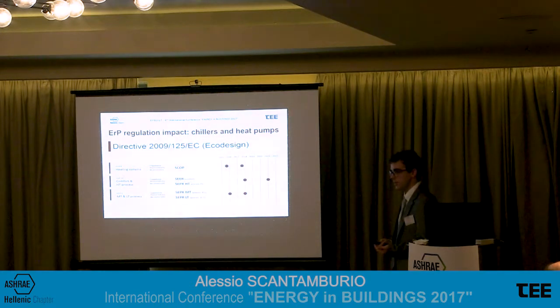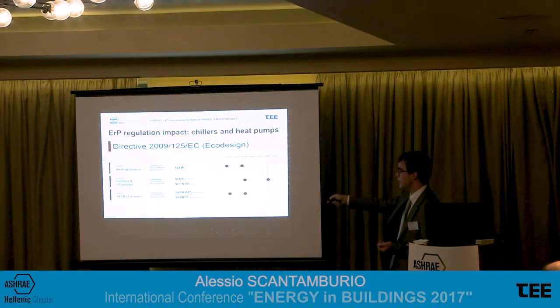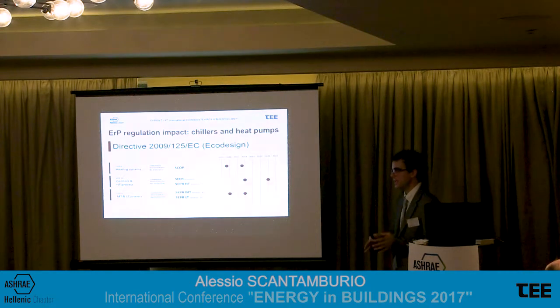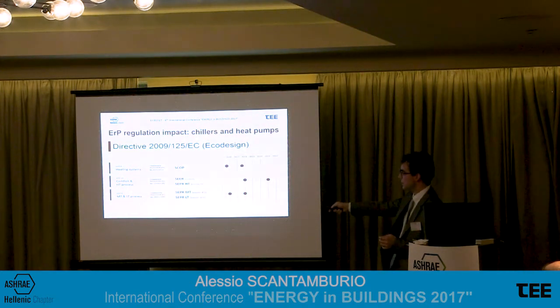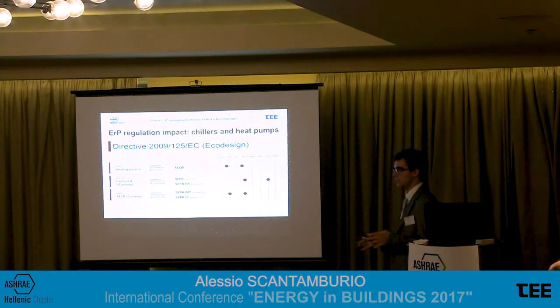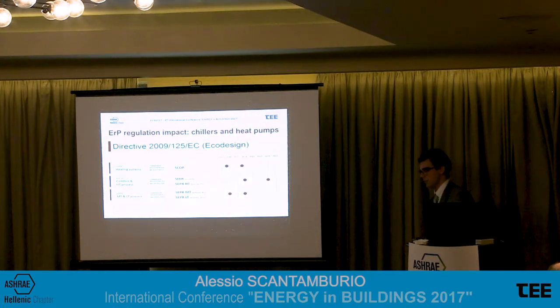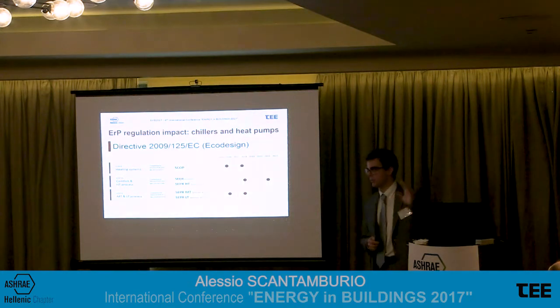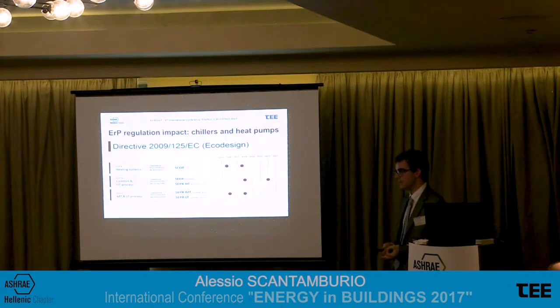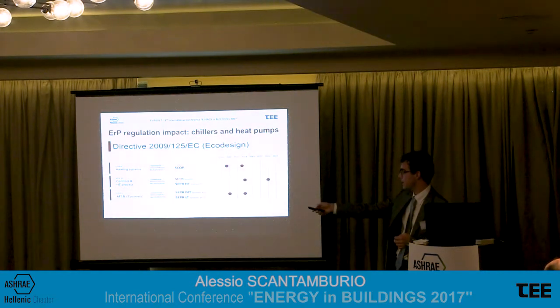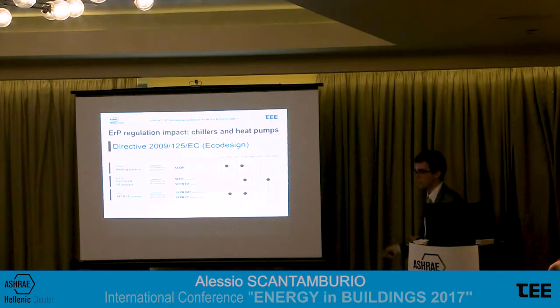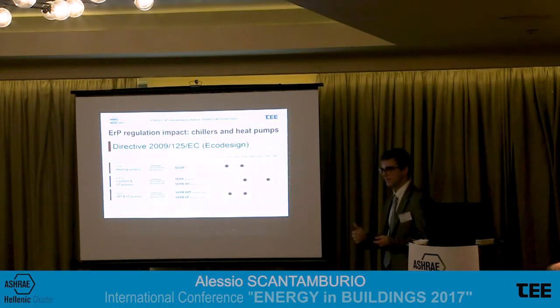If we are talking about a chiller, so a unit which produces cold water, we have 4 different parameters according to the applications. We have this regulation which covers SEER, so comfort cooling applications. Comfort cooling means I produce cold water for getting down the temperatures inside a building, for air conditioning. In this case the parameter is SEER, seasonal EER, and the first tier will start next January. And then we have a second tier in January 2021. Of course, the second tier is more demanding than the first one.